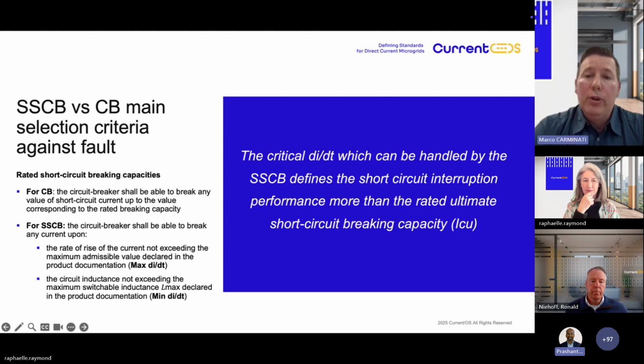You know that for both AC and DC application, a traditional electromechanical system shall be able to break any value of fault, in particular short circuit current, up to the value corresponding to its rated short circuit breaking capacity, often called ICU, with a specific power factor if you are in AC and a specific time constant if you are in DC.